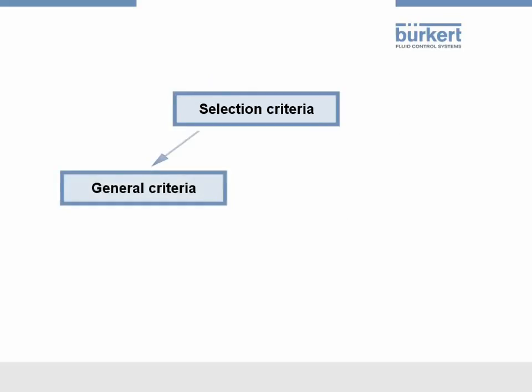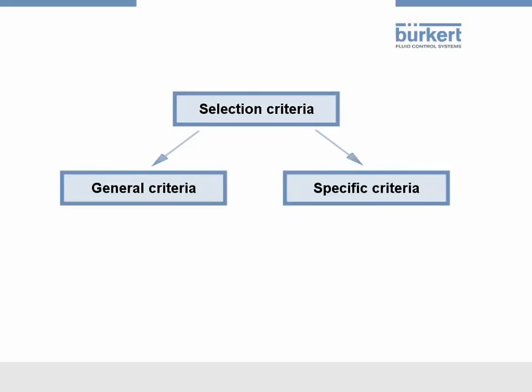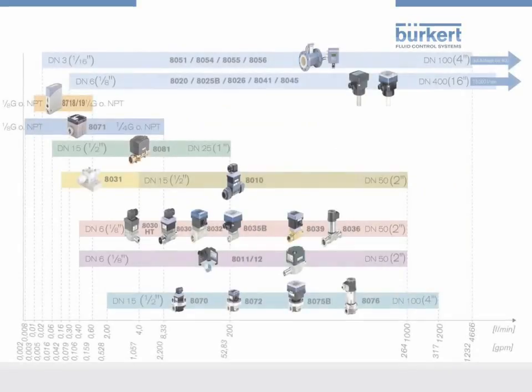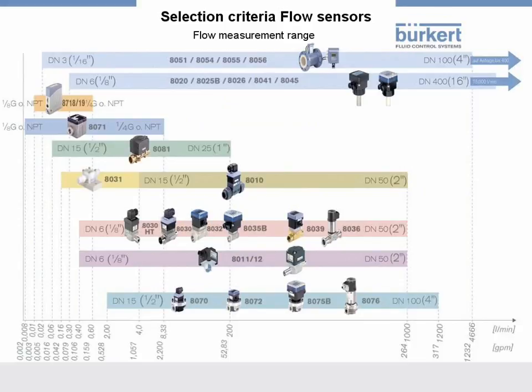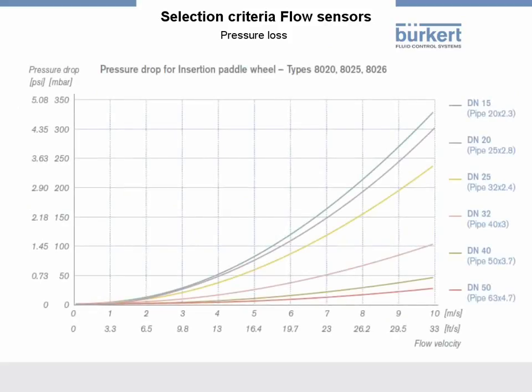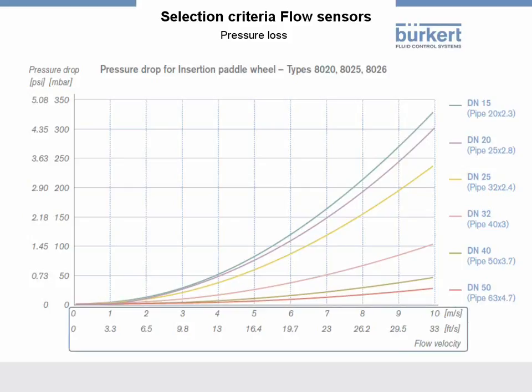In addition to the general selection criteria for flow measurement, there are also numerous specific criteria which we'd like to mention. The first criterion is the flow measurement range from the start to the end of measuring, which is different for the different measuring principles. The next specific criterion is pressure loss. Systems for generating pressure are expensive with respect to both construction and operation. Therefore, plant operators are interested in sensors that cause only a small pressure loss. The order of magnitude of pressure losses for flow sensors is shown in the diagram, based on the example of an insertion paddle wheel. The pressure drop primarily depends on the flow speed and on the pipe diameter.